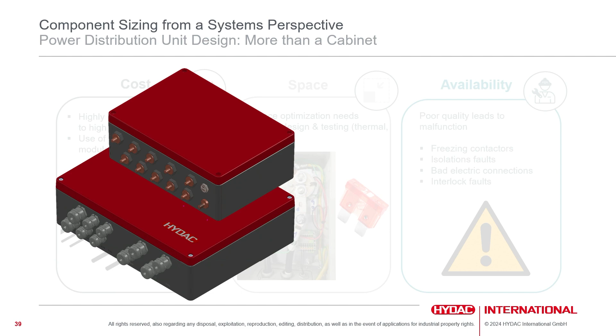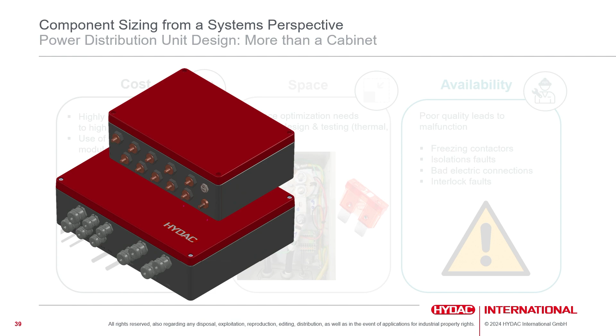And usually you have to do that when you are in vehicle production, which is not really nice. So one idea we brought up over the last projects is to change the concept of contacting and to have these kinds of board contacts on the outside of the PDU. So you can mount the PDU to the vehicle and connect the cables, the inverter cables, the charger cables, the battery cables, afterwards. So you don't have to open the PDU, you don't have to do complex assembly, you just have to contact the cables like you know it from low voltage inverters, typically.